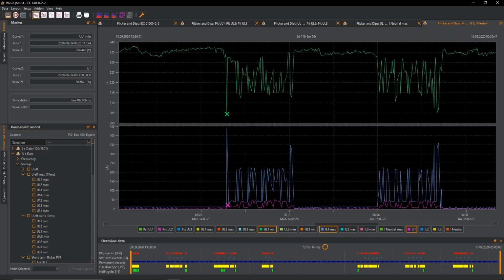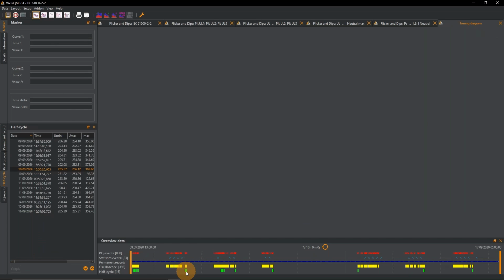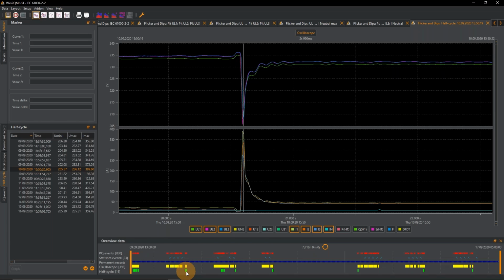And now I'm going to show you 3 easy ways to get to the desired data you want. So first, I can again focus on the overview data, and I could click on, for example, the green marker over here. There's a half cycle event, so the 10 milliseconds, and the trigger is supposed to be a dip on voltage on phase 2. So I will just click on that and it opens me a timing diagram. I have my trigger line in the white vertical line here.